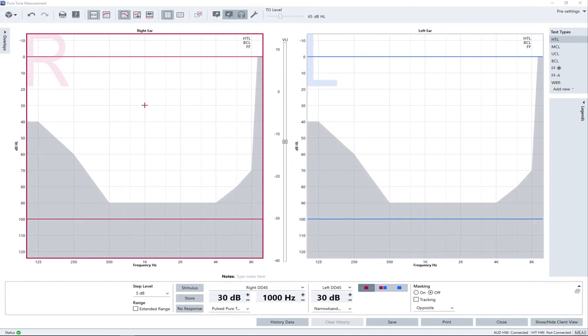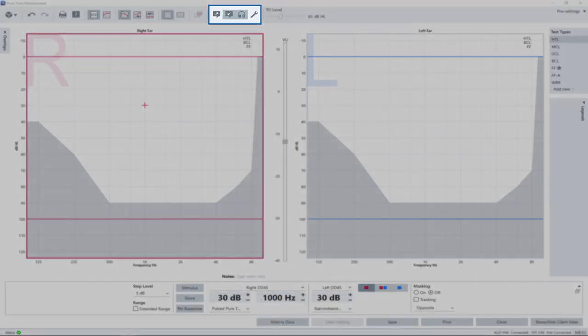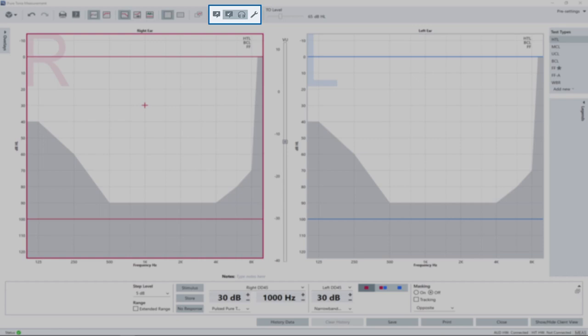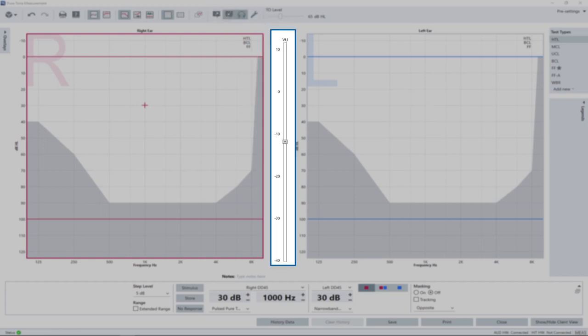The talk over function is accessible either from the top panel or from a dedicated shortcut key on the keyboard. The microphone works as press to talk function. Adjust talk over microphone sensitivity with the slide on the VU meter to meet 0 dB input while pushing the talk over shortcut key on the keyboard. The talk over level in the client's headset is adjusted in units of dbHL with the slider control located in the top panel.